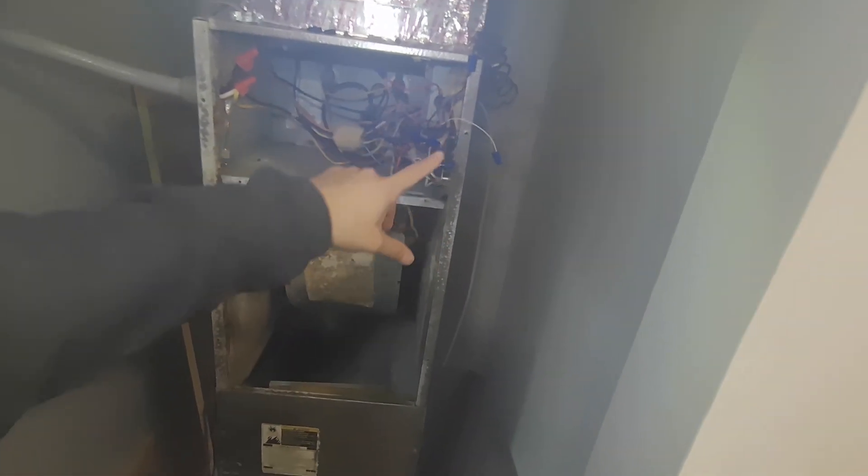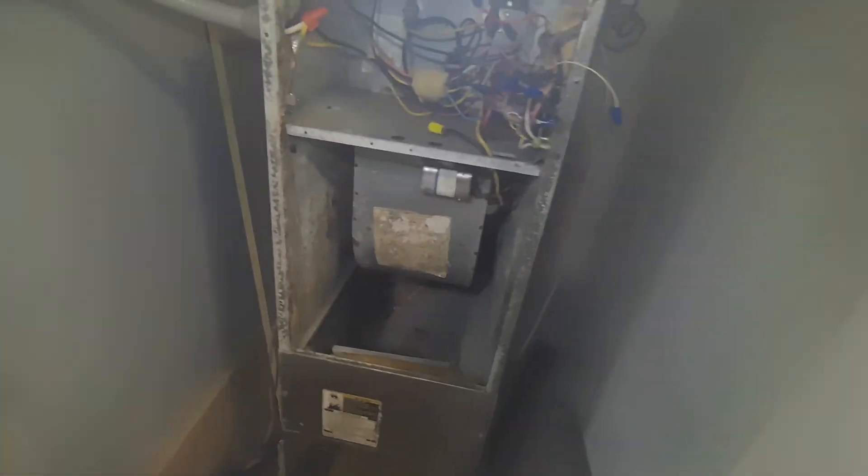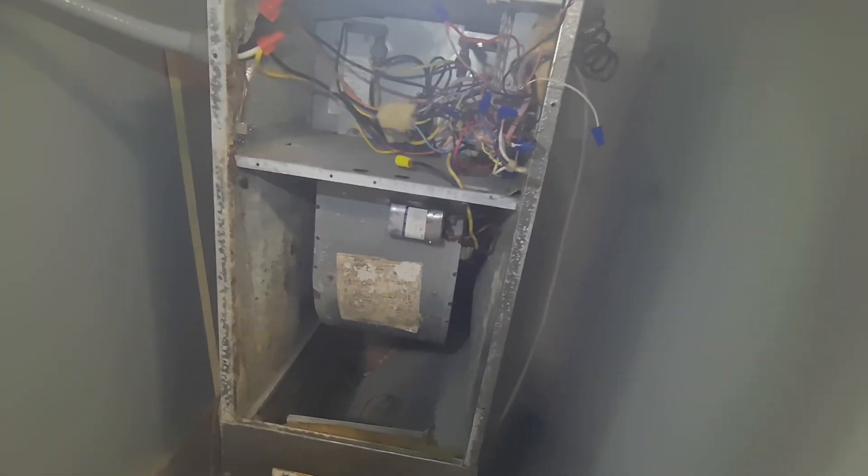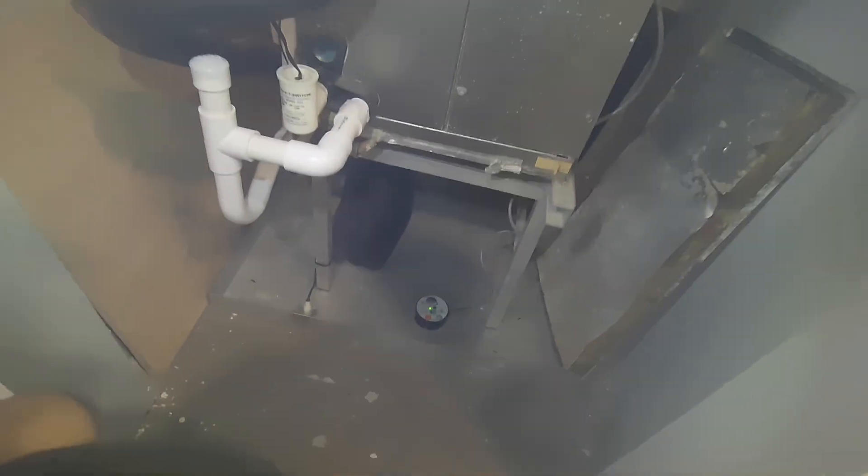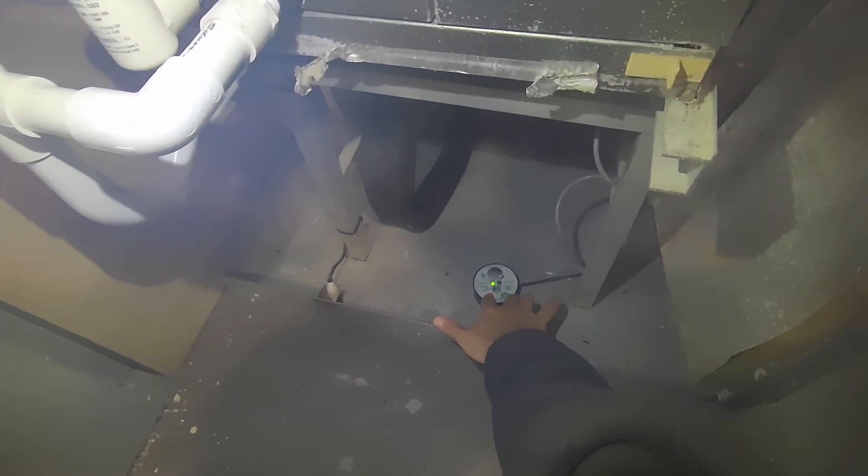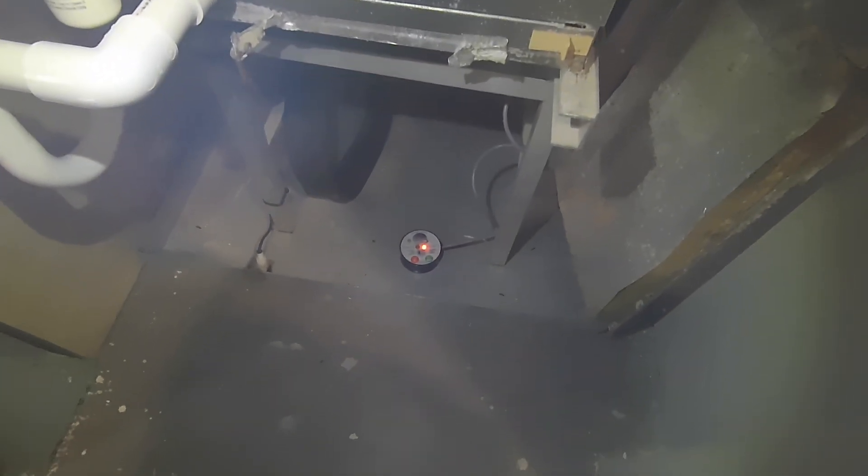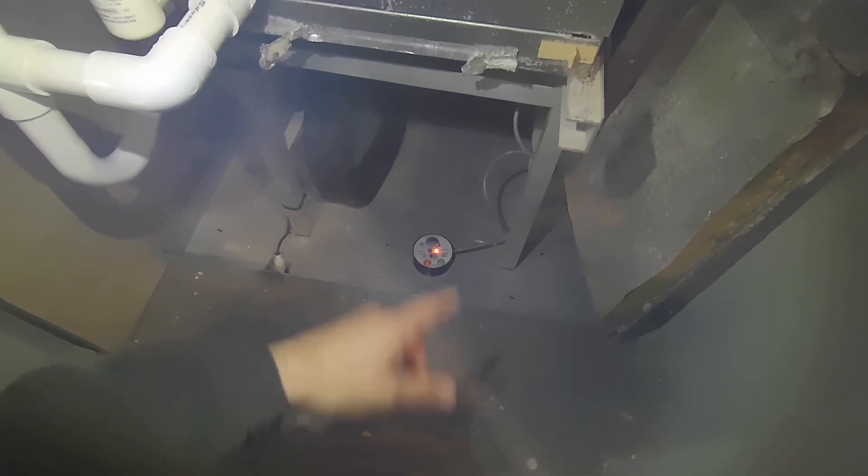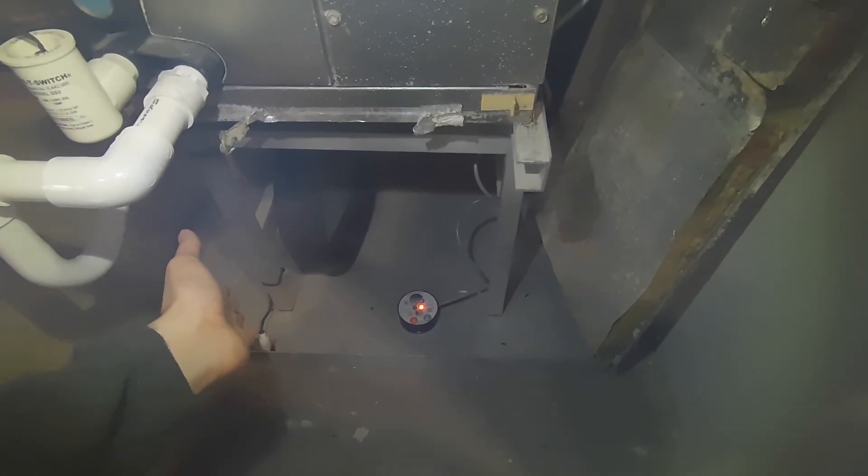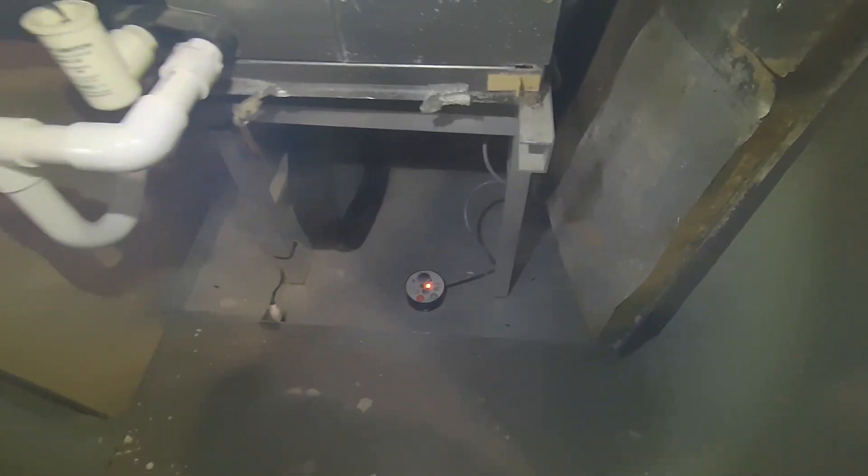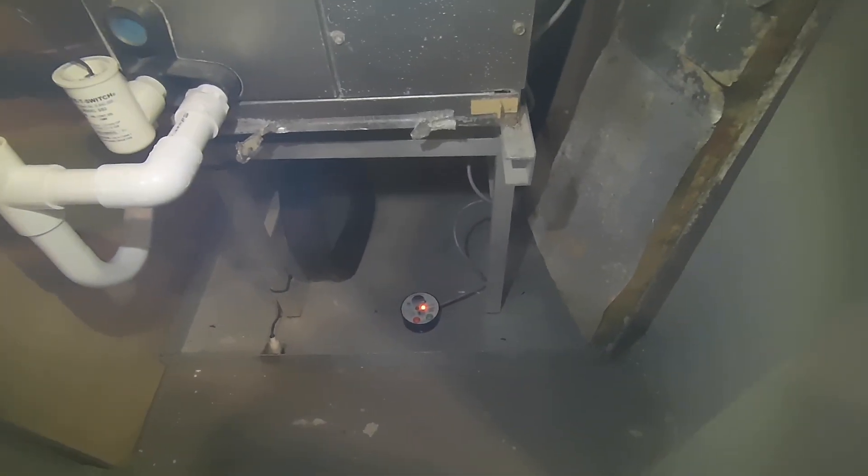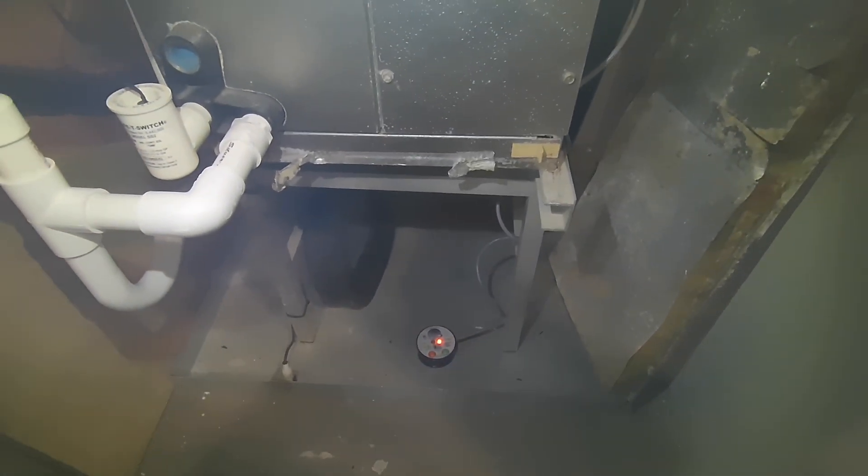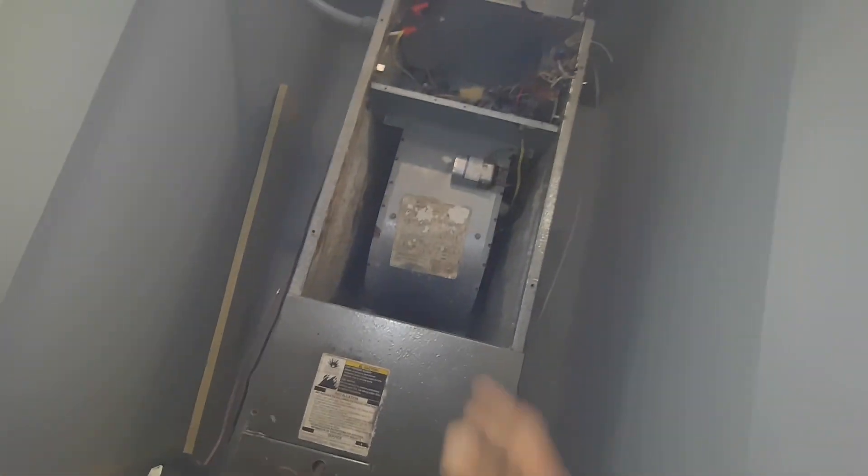So we have 24 volts making its way to that fan to call it to turn on. Now what we do, we come down to the switch, push to test. Now that's basically giving us an idea that it's turning off, that it cut the power, so it's not going to allow any more 24 volts to come through.